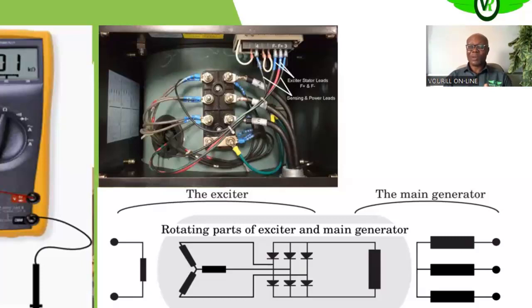If you have your normal voltage, and after you connected the AVR you are not having your normal voltage, it means the AVR has some problem. Once the inputs are there, you are expected to have the full 12 volts. So you can disconnect F minus and F plus and excite with your 12 volts battery, you are expected to have 12 volts here. Or you can take the AVR to do a bench test, supply it with 110 volts, and you expect to have 12 volts DC from these two terminals.